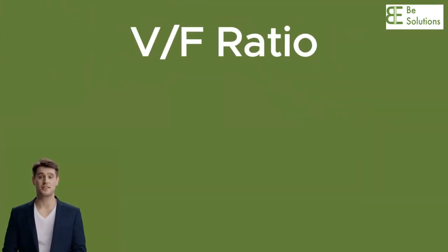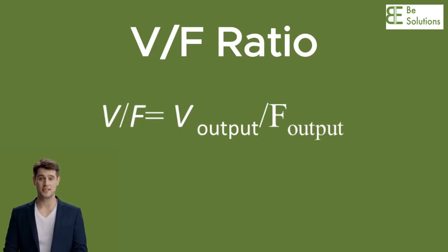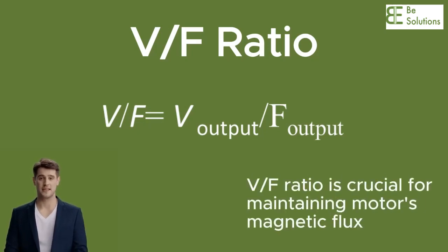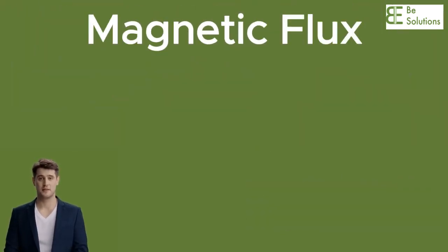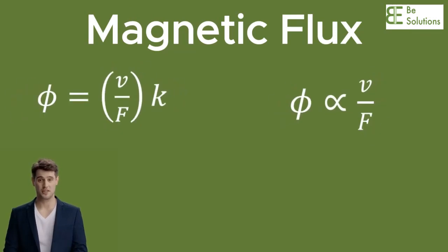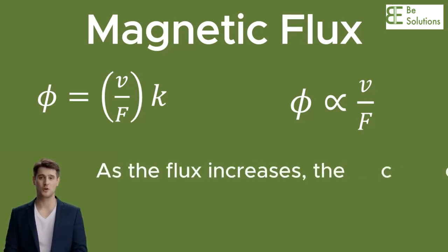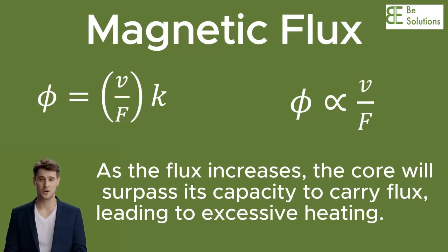In variable frequency drives, V/F ratio typically represents the ratio between the output voltage and frequency. This ratio is crucial in controlling the speed of an AC motor. V/F ratio is crucial in maintaining the motor's magnetic flux. If the voltage is not decreased proportionally with the decrease in its frequency, the flux will increase. As the flux increases, the core will surpass its capacity to carry flux, leading to excessive heating. So V/F should remain constant.